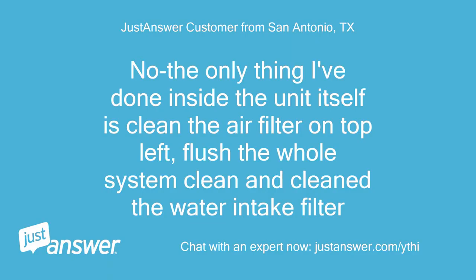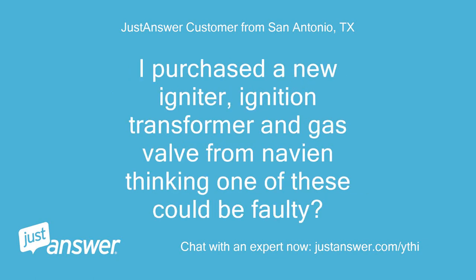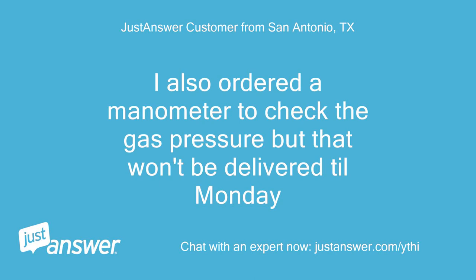No, the only thing I've done inside the unit itself is clean the air filter on the top left, flush the whole system, and clean the water intake filter. I purchased a new igniter, ignition transformer, and gas valve from Navien thinking one of these could be faulty. I also ordered a manometer to check the gas pressure, but that won't be delivered until Monday.